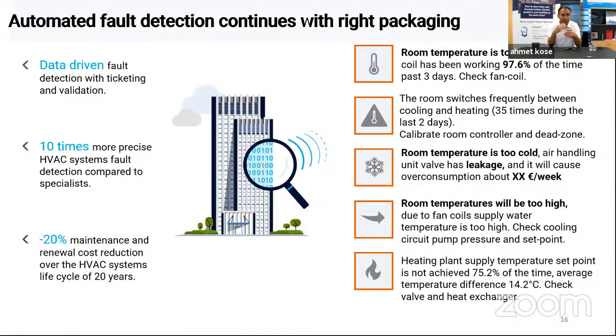The second thing is that actually everything is working, there is no mechanical failure, but there might be operational issues. If we use a very small dead zone or threshold for following the target set point, you'll see continuous heating and cooling. This heating and cooling comes from either radiators, fan coils, active panels, or other VAV systems, whatever is available in the building, but in the end they are all heating, cooling and ventilation items.